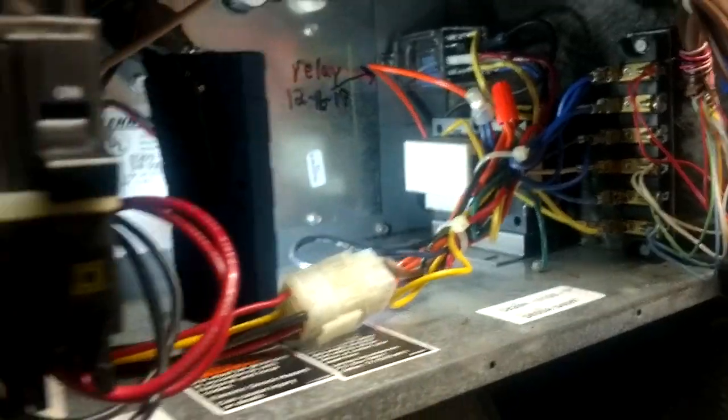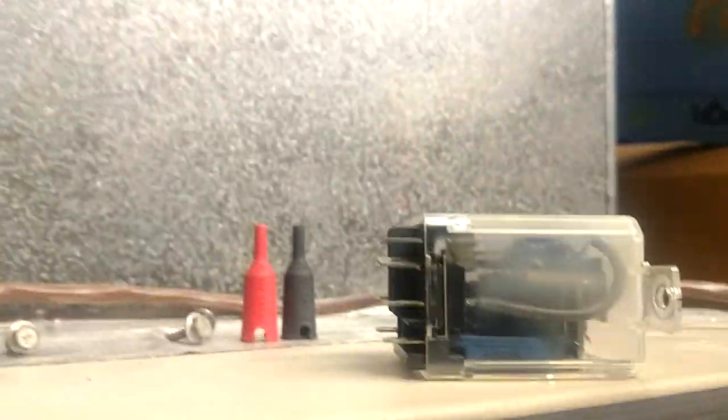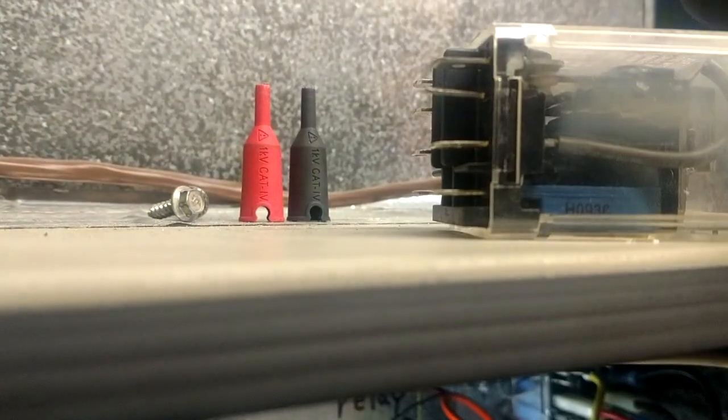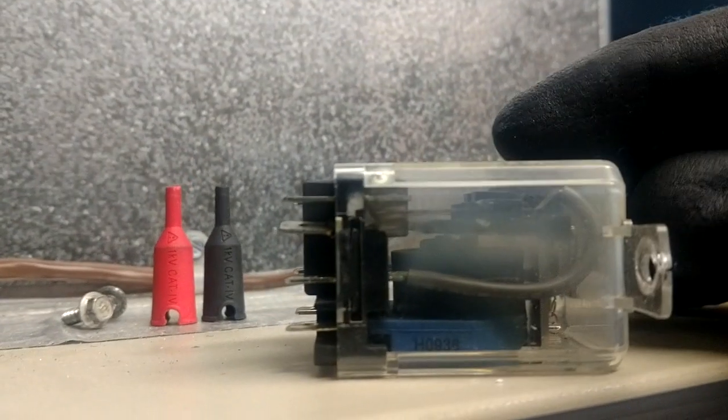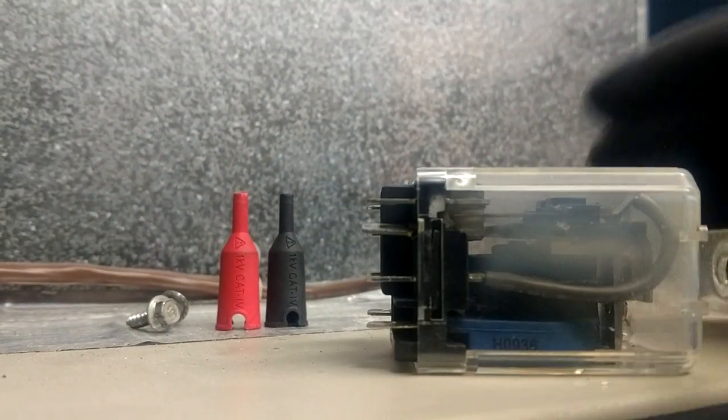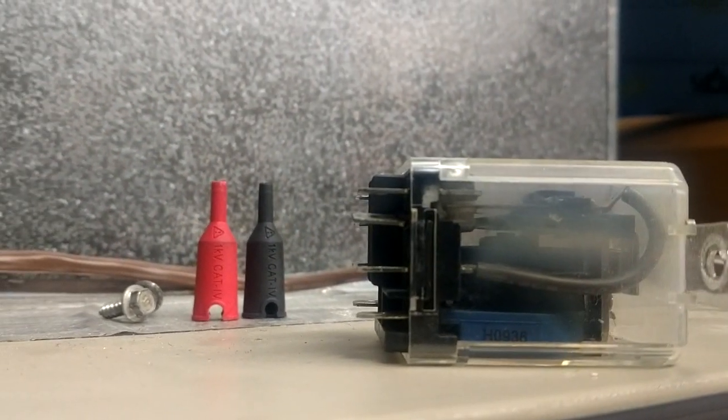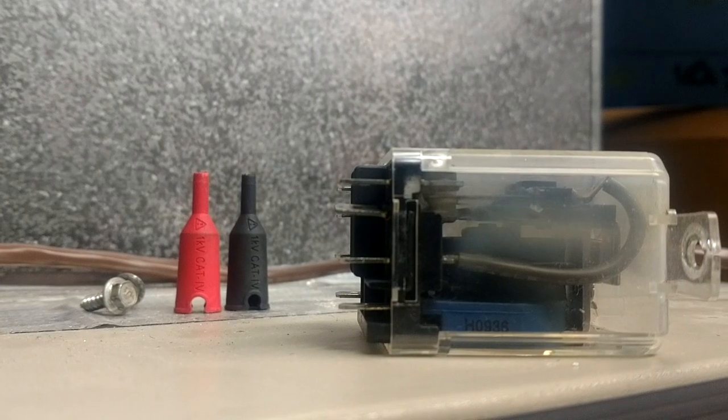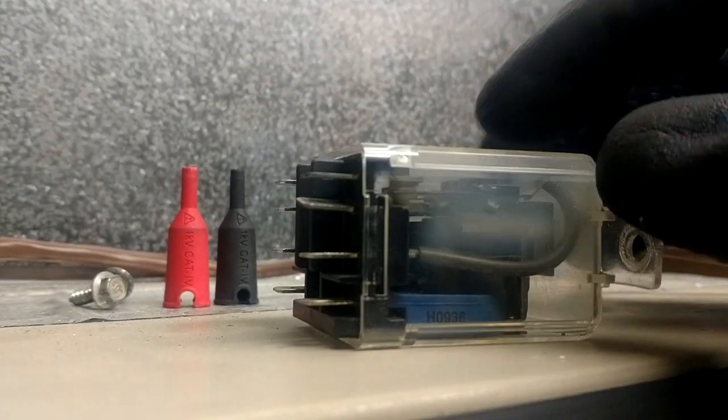All right guys, we're just going to make this little part two video. We've got this old relay out. If you just watched the other video I did diagnosing the relay in there, you can see that this side is definitely burned up. If you looked in there, the contacts are all bad. There's some burn places right there.